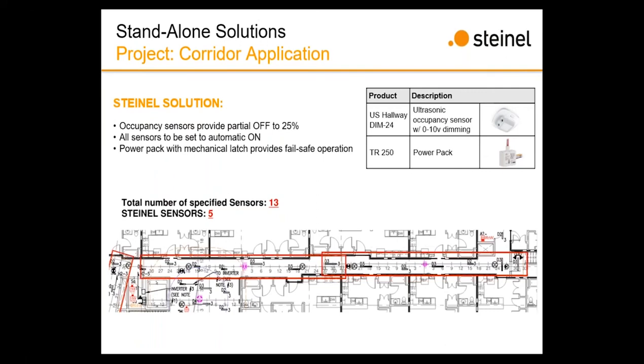The hallway sensors are definitely my favorite sensor because of the partial off capabilities they offer. In a corridor, you typically never want the lights to go off. Most of our competitors require a room controller for this, but we are able to do 100% during occupancy mode and 50% during vacancy mode utilizing just standalone components—simple 18/3 wire, power pack, sensors, and our Bluetooth to IR remote for ease of commissioning in the field. No room controllers required for the simple standalone setup.